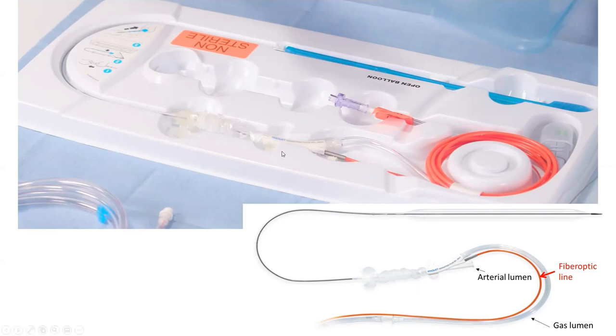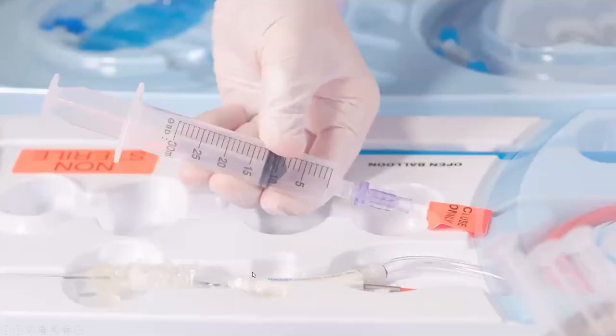What we do here on this tray, you flush that arterial lumen here, and you put negative suction on the helium lumen here. This gas lumen, you connect it to this valve and you put negative suction with a 30 milliliter syringe and you disconnect the syringe here while holding negative pressure. That valve will hold the negative suction on the balloon. This will allow you to advance the balloon more easily. Okay, so you do that negative suction. Eventually, when you're in the body, you remove that valve and you connect the tubing to the console.